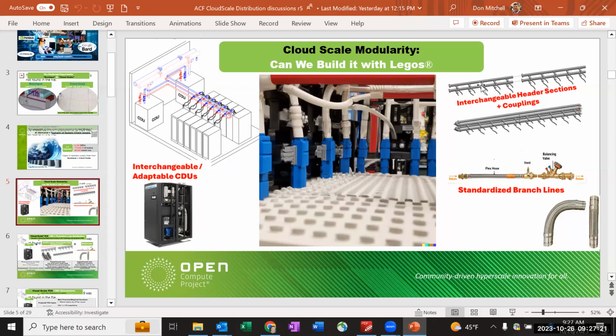None of the plumbing changes, but the filter inside the in-cabinet pump system, if it's designed well, you could pull out the 100 micron filter and plop in a 25 micron filter. Now 90% of the servers in there are getting coolant that's way cleaner than necessary, but the least-common-denominator server with microchannel heat sinks or cold plates is now happy with the coolant quality.